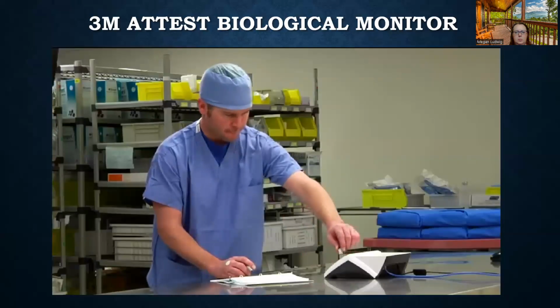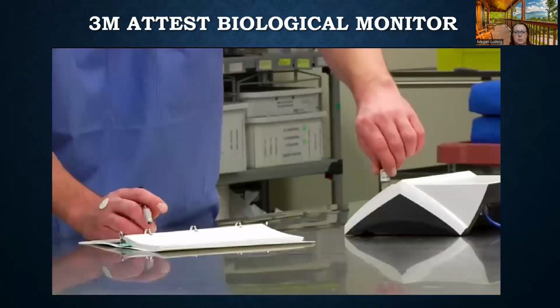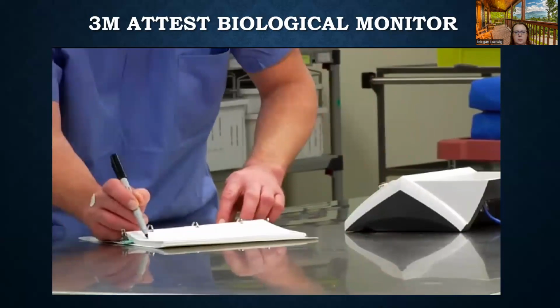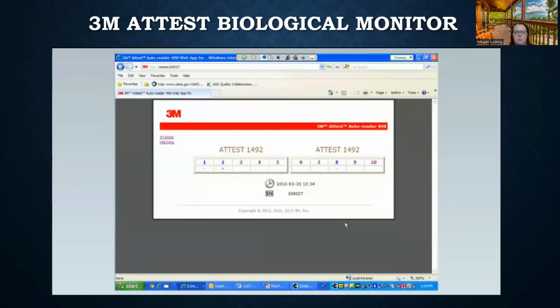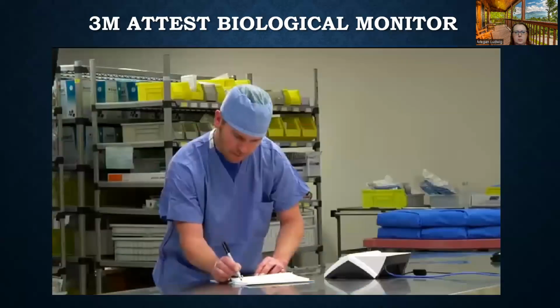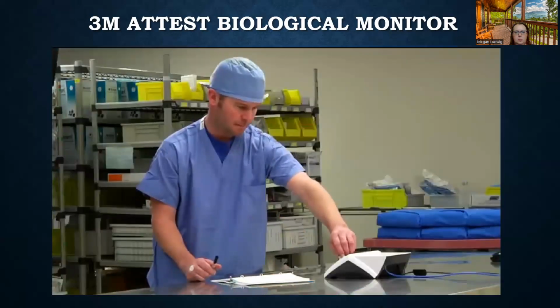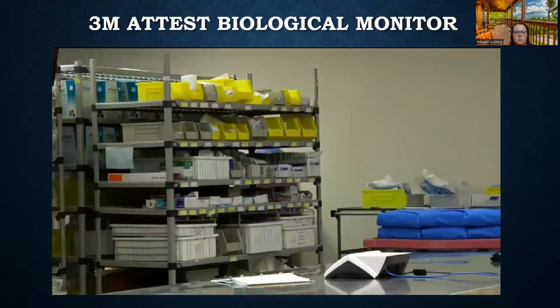After a BI test is complete, the next step is to record your results. You can use traditional record-keeping methods or the 3M Attest Auto-reader 490 web app. The 1492V BI is normally discarded after the fluorescent result has been recorded.